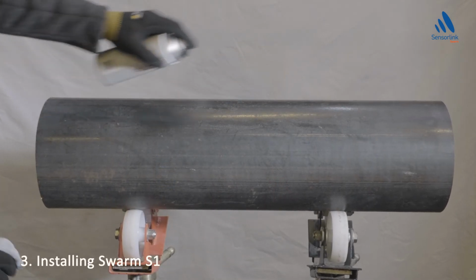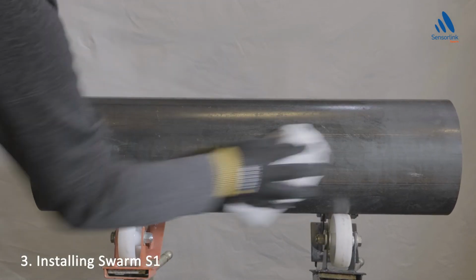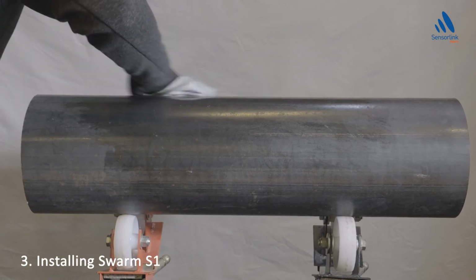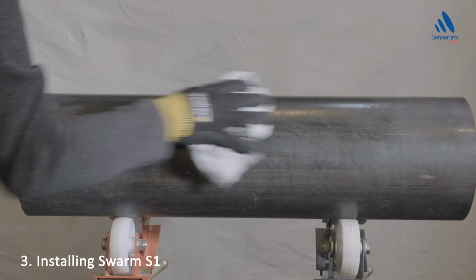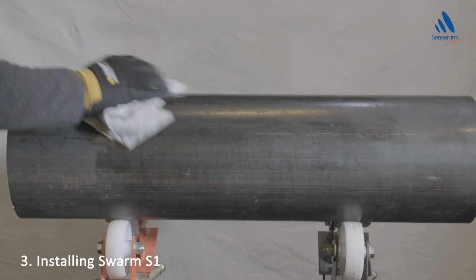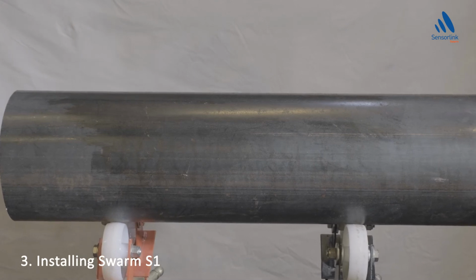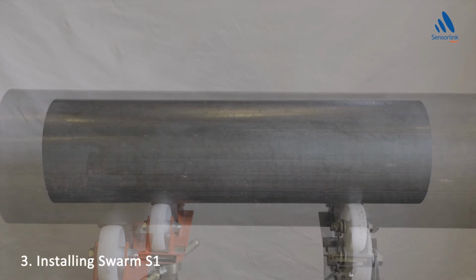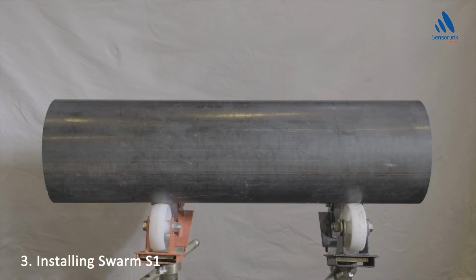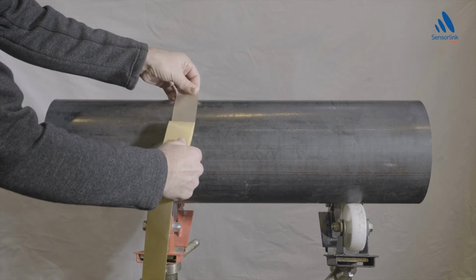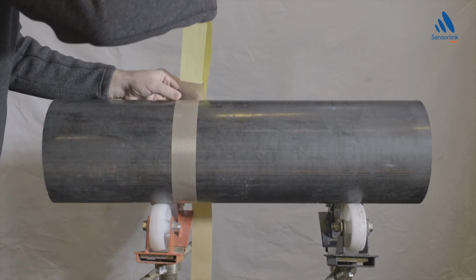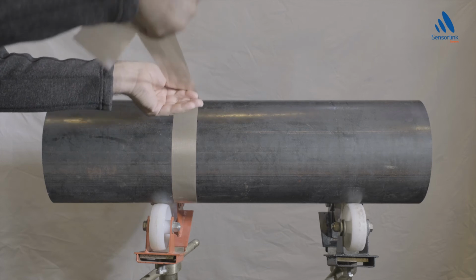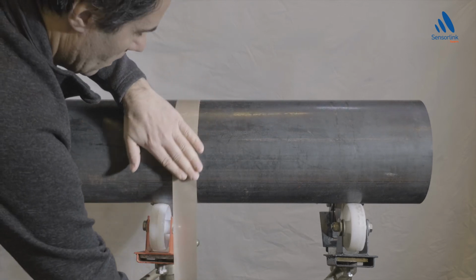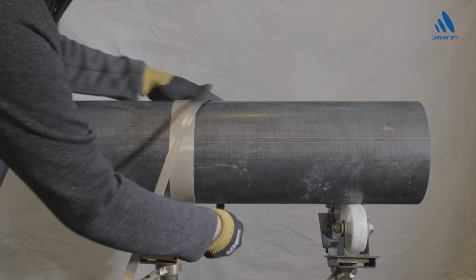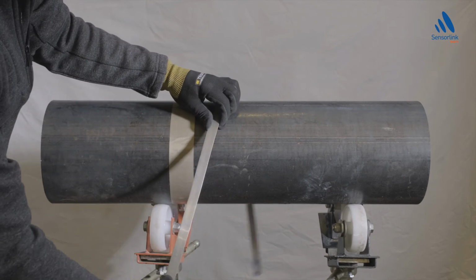We will now show how to install the Swarm S1 sensors onto the pipe. Normally, the only preparation needed is to clean the pipe. If installing the Swarm S1 sensor on a weld, the weld cap might need grinding to ensure good acoustic contact, but only do this after agreeing with the client. Start by measuring approximately the length of the galvanic insulation tape. Fasten the tape onto the pipe. Cut the length of the steel band from the reel approximately 60 centimeters longer than the circumference of the pipe.